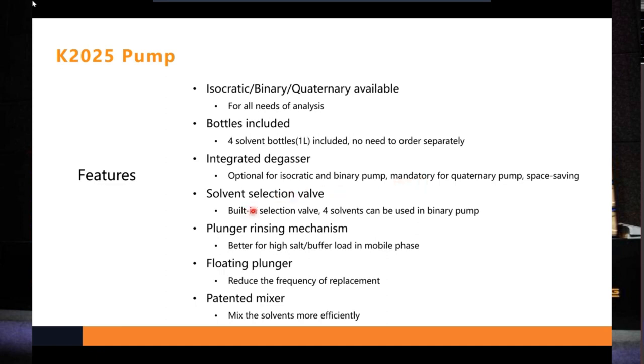And the pump is also equipped with a solvent selection valve. It can be used for automatic selection of up to 4 solvents for the binary pump. We don't have a solvent selection valve for the quaternary pump. And the plunger rinsing mechanism is for the cleaning of the plunger and plunger seal. It is self-operated, runs 5 seconds for every 40 seconds. So it is better equipped for high salt buffer loading in the mobile phase.